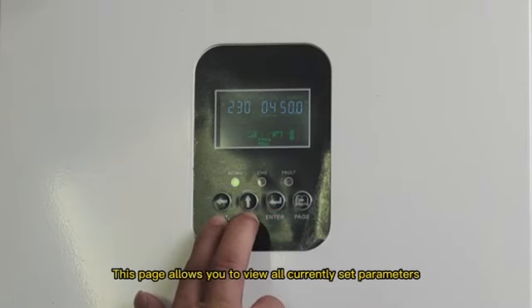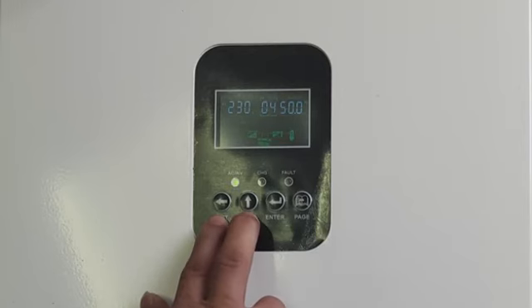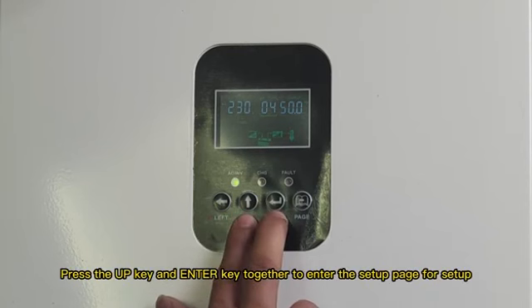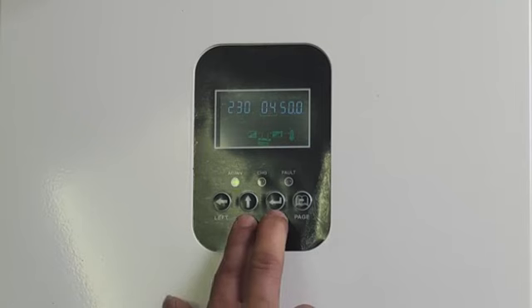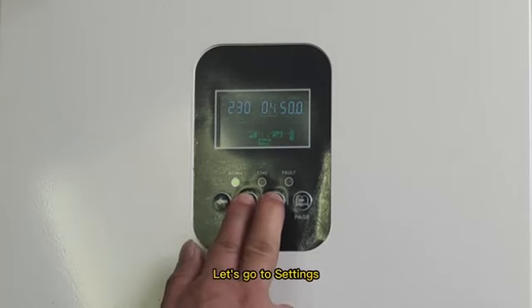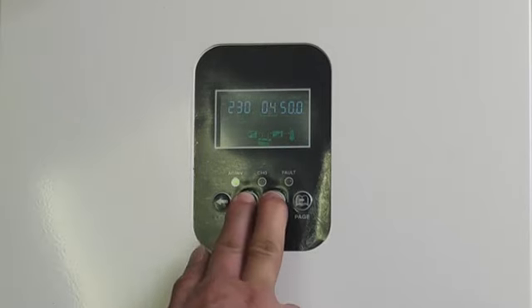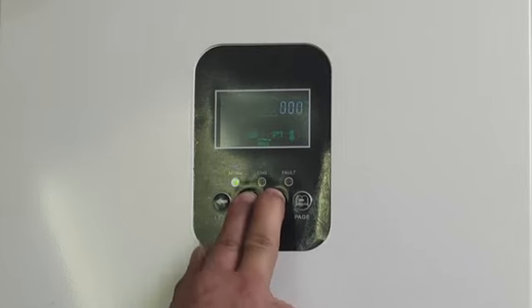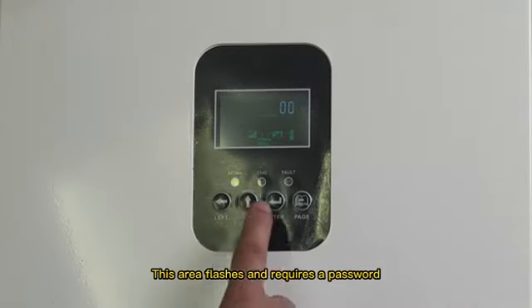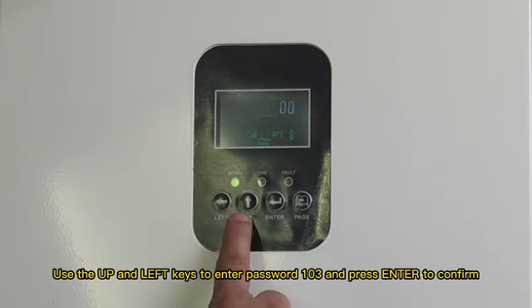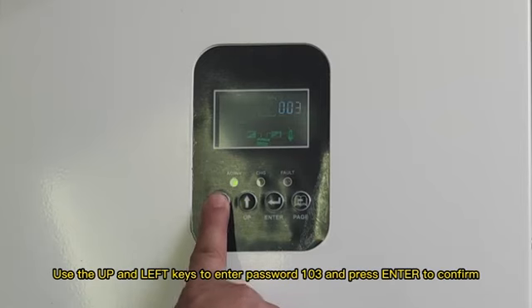This page allows you to view all currently set parameters. Press the up key and enter key together to enter the setup page for setup. Let's go to settings. This area flashes and requires a password. Use the up and left keys to enter password 103 and press enter to confirm.